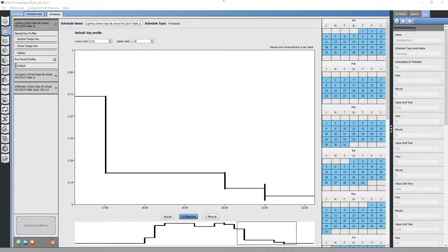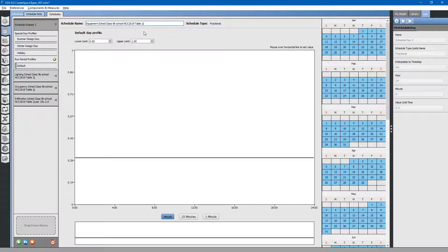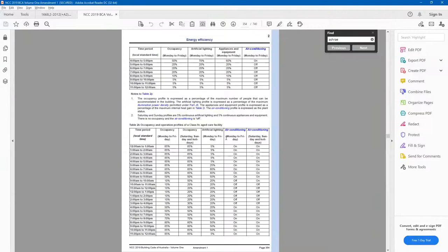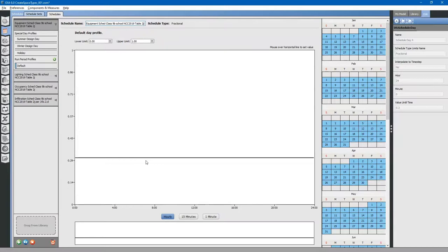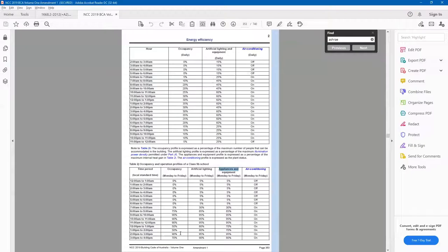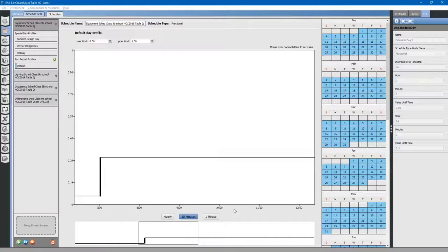Finally we need to create an electrical equipment schedule. We'll rename it to our equipment schedule and do another fractional schedule, renaming it based on Table 2J. Looking at appliances and equipment: midnight to 7 is 5 percent, and 7 to 8 is 30 percent.